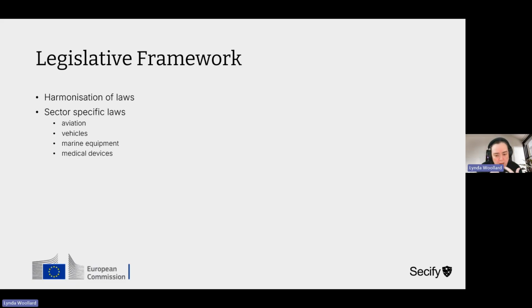With regard to the Cyber Resilience Act, when we look at the scope, some sectors are exempted from the Cyber Resilience Act, or have a limited impact from it, because they are already covered by sector-specific laws. So the aviation sector, vehicle sector, marine equipment, medical devices, and in vitro diagnostic medical devices are specifically covered by different pieces of legislation that set out security requirements for those devices. As such, the Cyber Resilience Act does not necessarily apply to these sectors where those particular pieces of legislation already set out an equivalent level of protection.